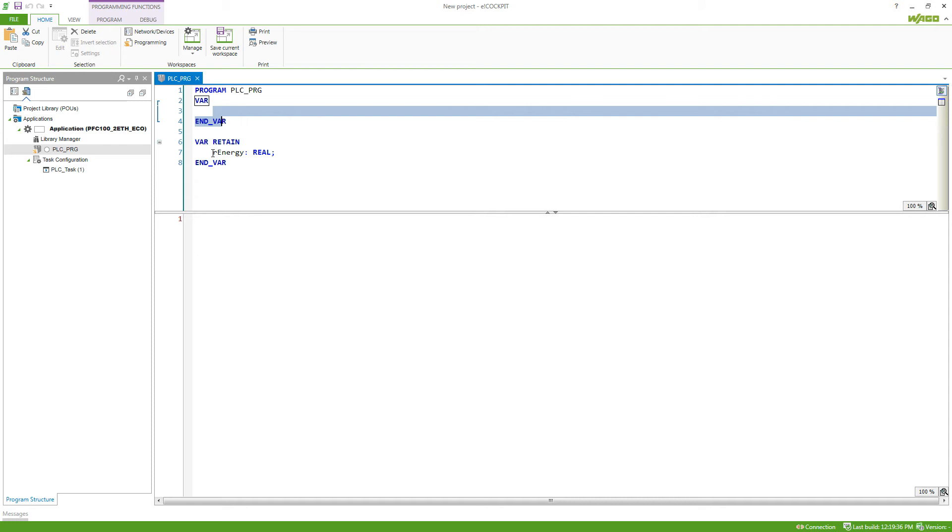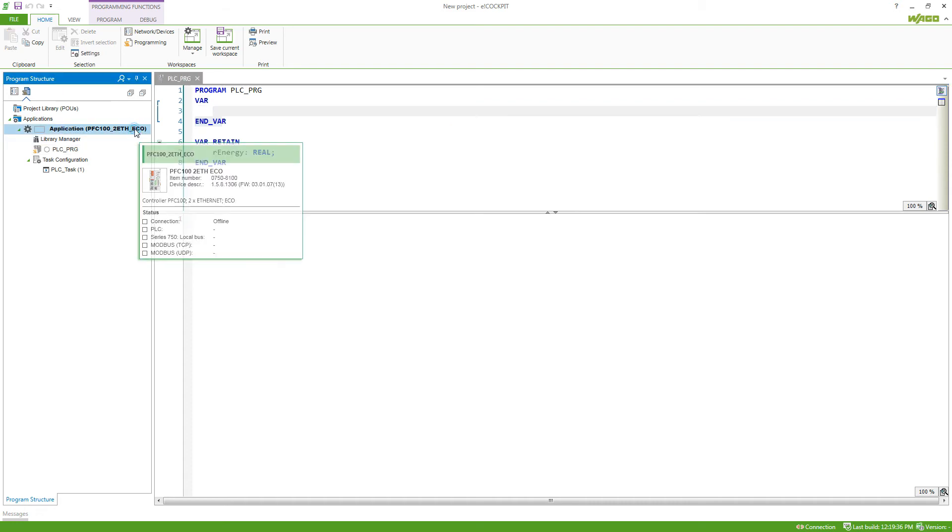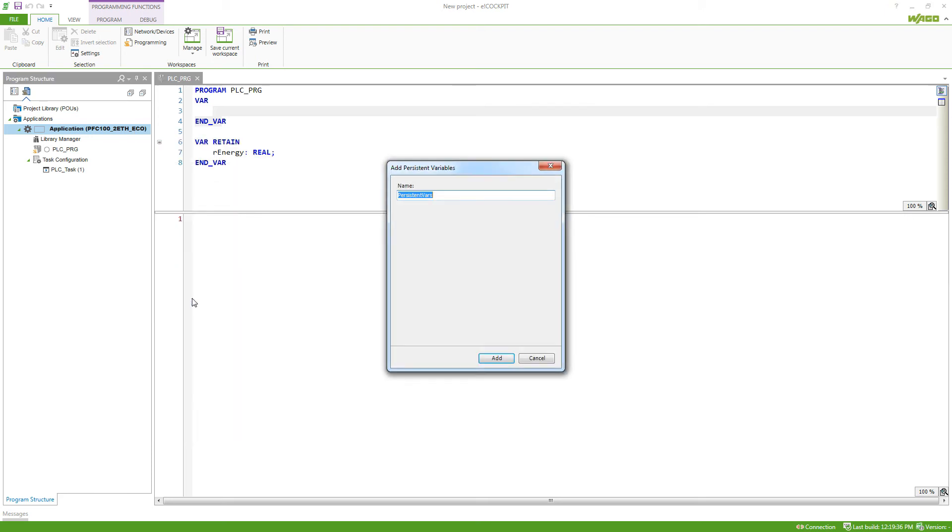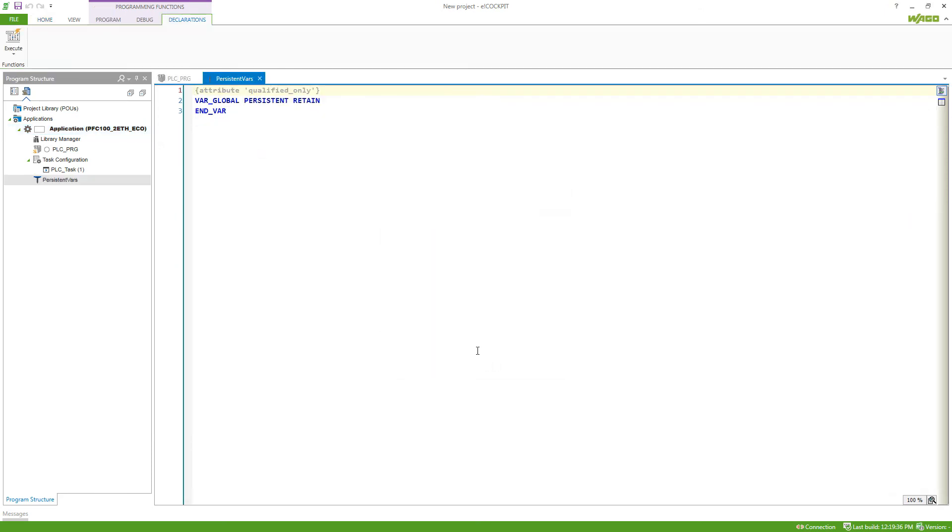In order to have a variable persistent, we need to have a special variable list in our program where all the persistent values are listed. We do right click and then say persistent variables. If we add this list, this looks just like a global variable list and we can use it in the same way.